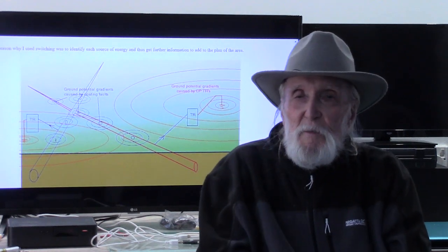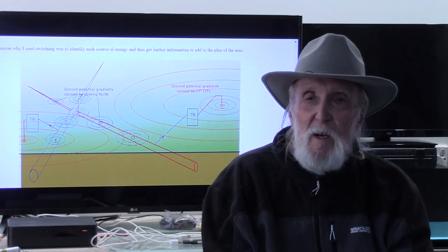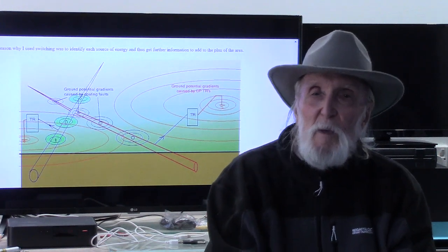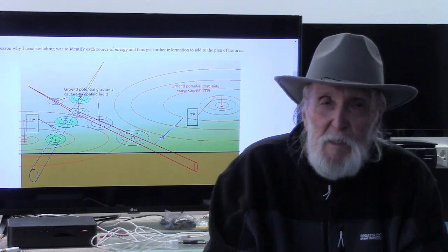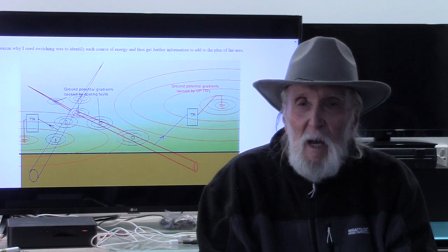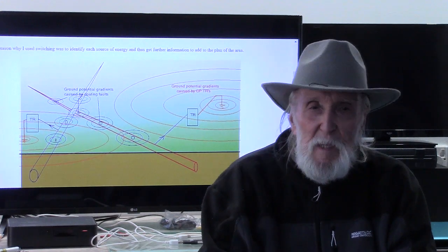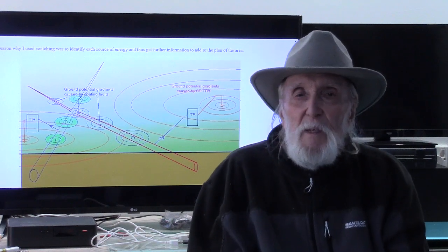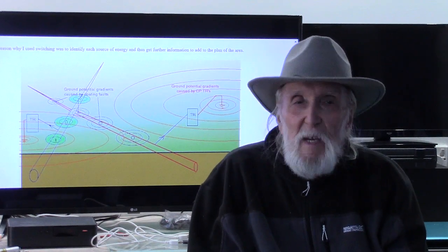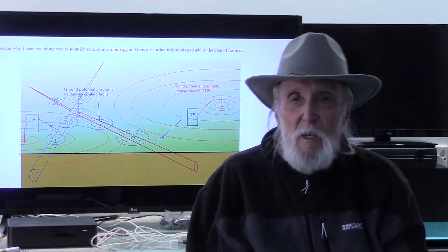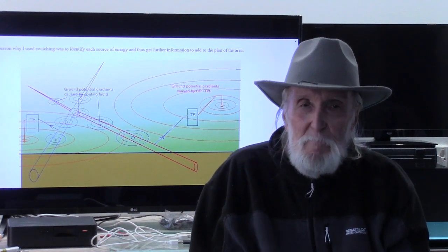It is important to recognise that in an area of over 1.6 volts, the ground potential would show a depression in the potential with the impressed current switched on, and this would reverse to a peak when the current is off. This feature is easily recognised in a 2 half-cell survey grid plot with the TR switching.